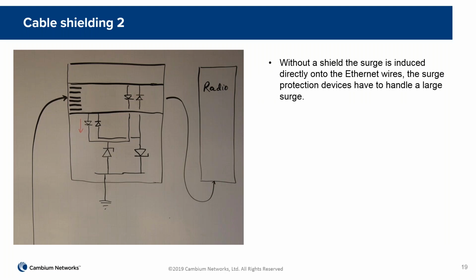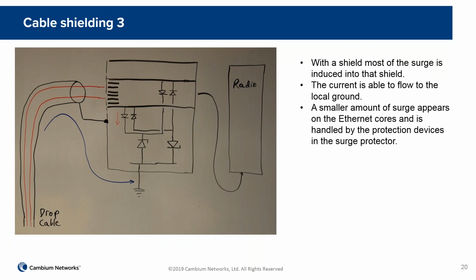As I mentioned, we have a current which at the moment is going into just the inner cores of the cable. We want to make that current really be in the outer of the cable. So with our screened cable, we now have a situation where most of the current is induced in the outer and it flows harmlessly to ground. Residual surge, some of that's coupled into the inners of the cable, is then intercepted by the surge protector in the normal manner. But what we've done here is to reduce the burden on the surge protector, or to put it another way, we've increased the capability of the system to withstand surges.